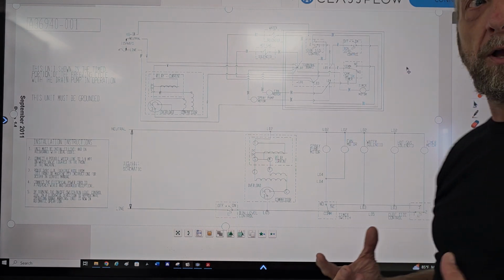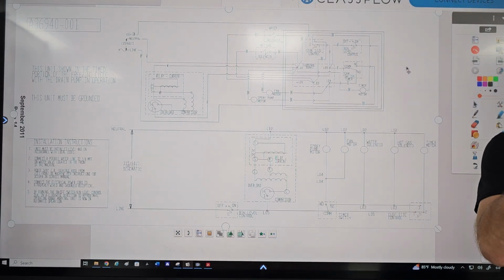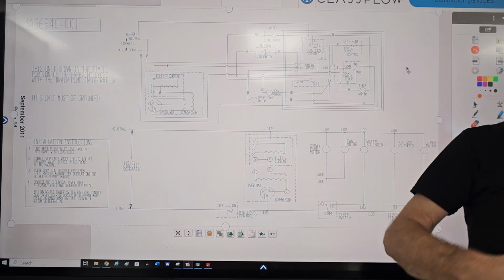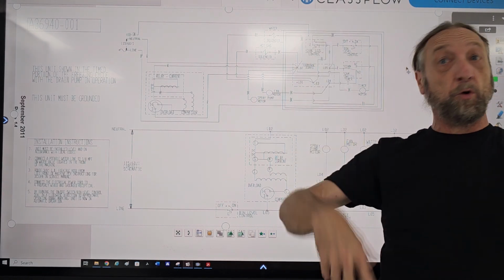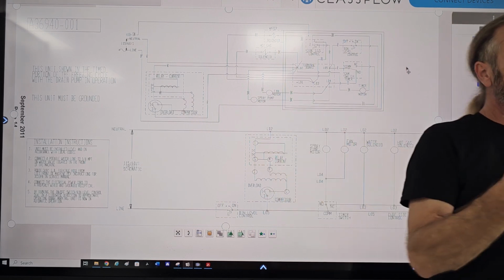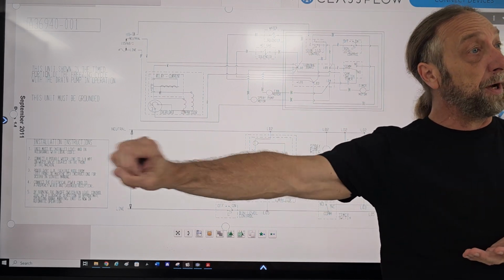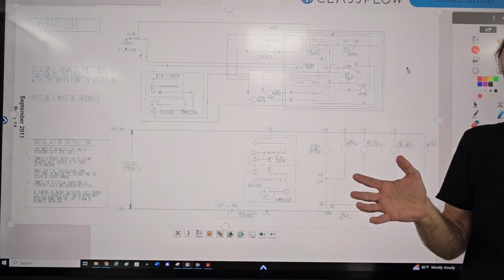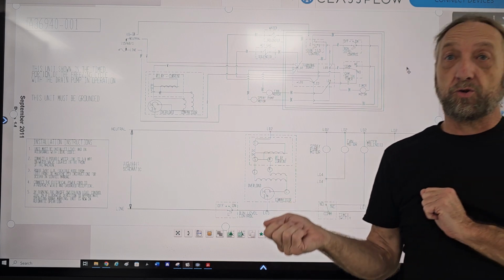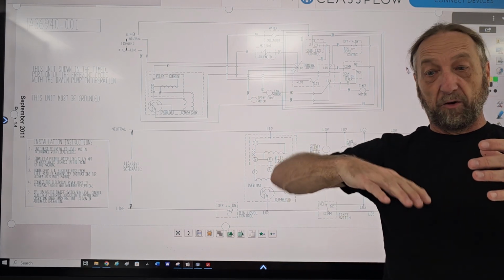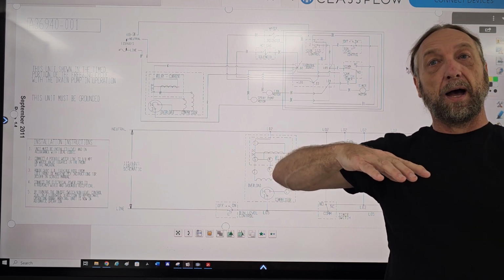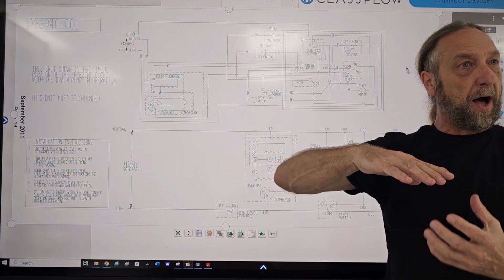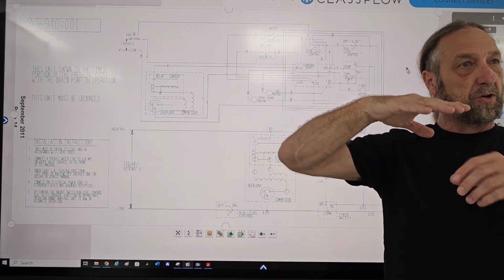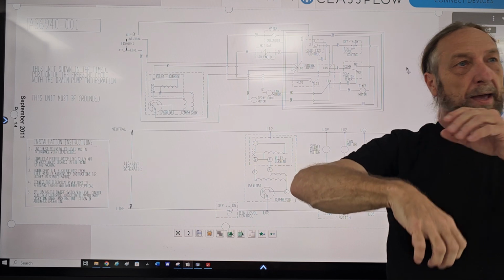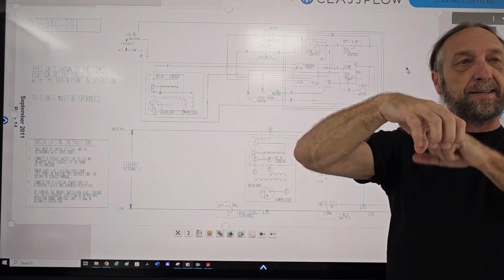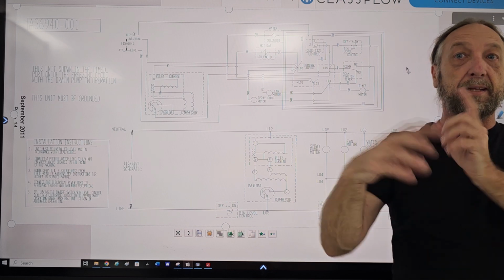They use them in central air systems — say you have an older home where the only closet is in the middle of the house, and you put your AC unit in there. The AC collects moisture and needs a pipe to drain outside. If you don't have a way to run a drain from the center of the home, they use a separate box with a float and a pump inside. When the AC drips water into the box, the float rises, and at a certain level it hits a switch, like a float in a toilet bowl. That switch turns on the pump, and there's a second switch that turns the pump off once the water level drops low enough.